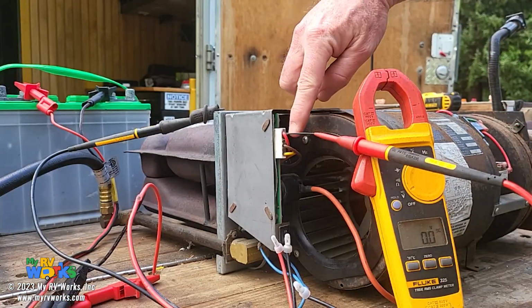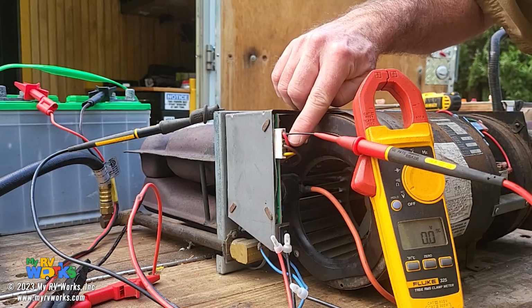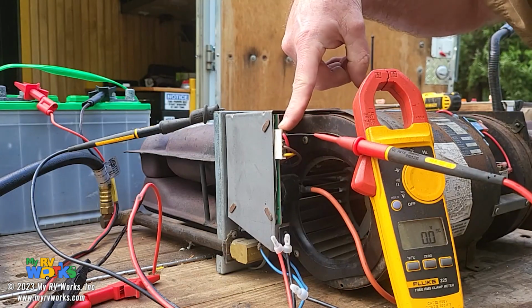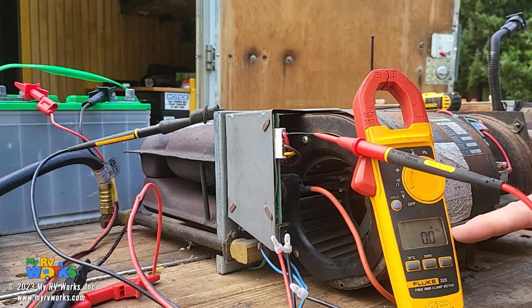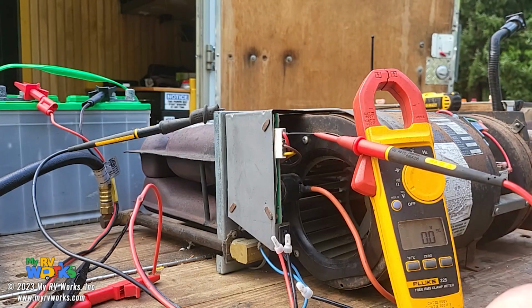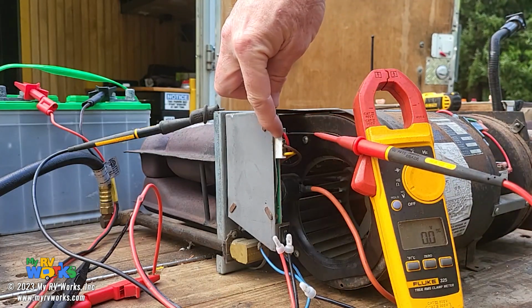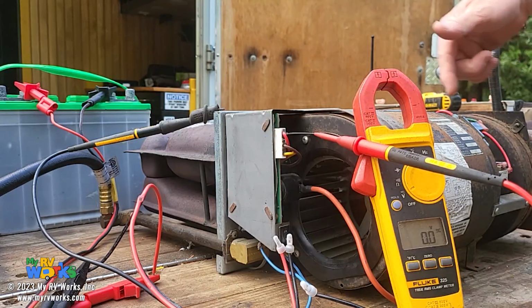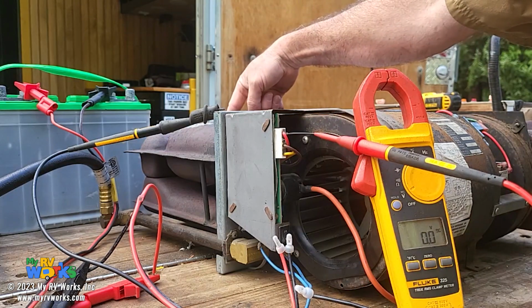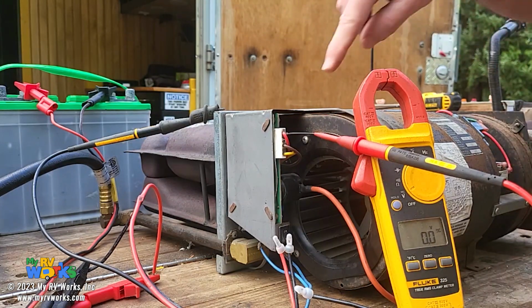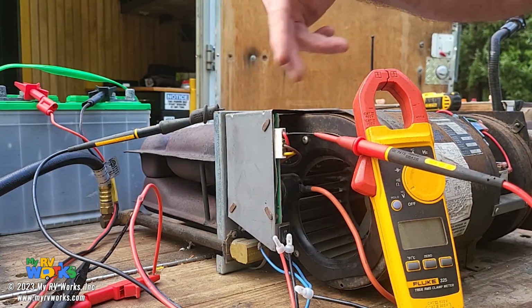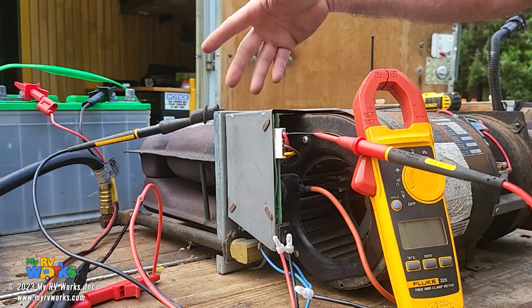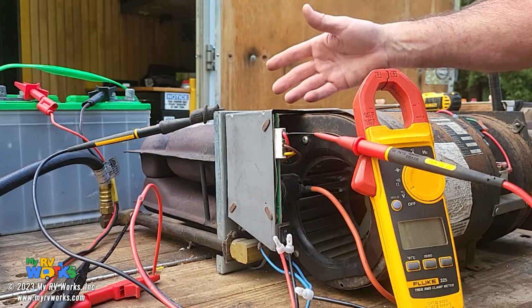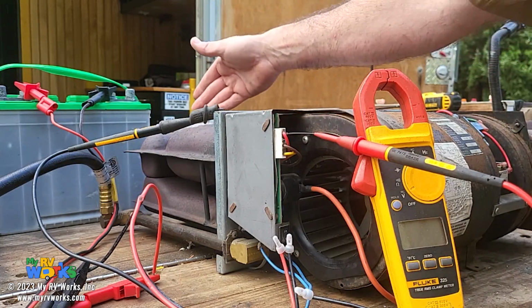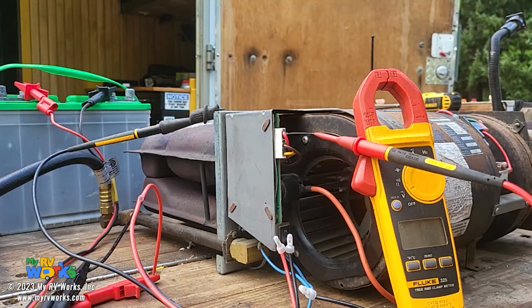Now I've got my pin, and what we're looking for is voltage on this red wire coming into this white connector, and you should be able to see the meter down here. If there's voltage on the red wire, that tells us current has made it through the high temperature switch in the back, made it through the sail switch, and is now telling the board it's okay, like fire in the hole. There's a call for heat, I'm not overheated, and my sail switch is happy. So we're going to connect these two together again.